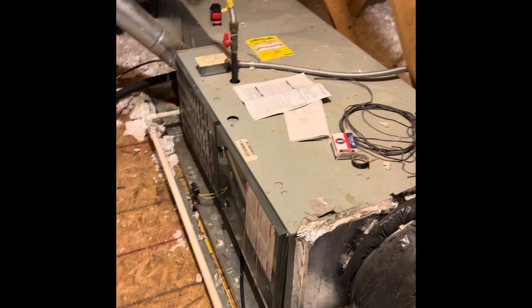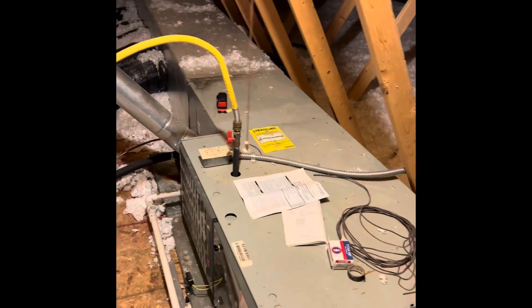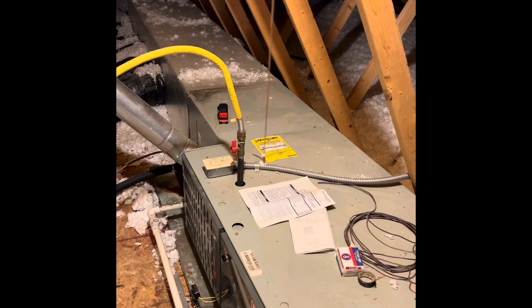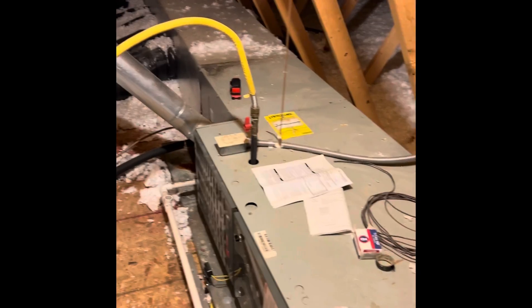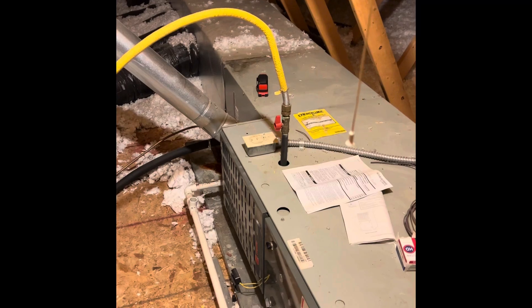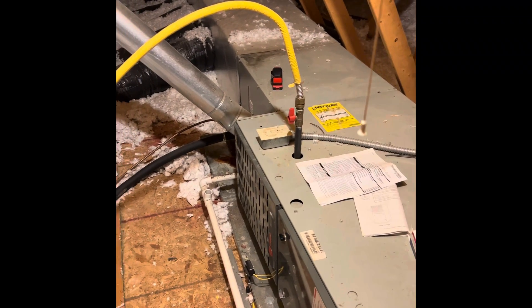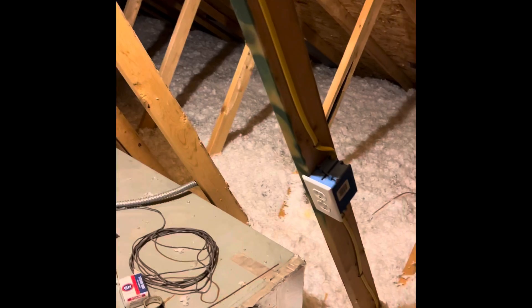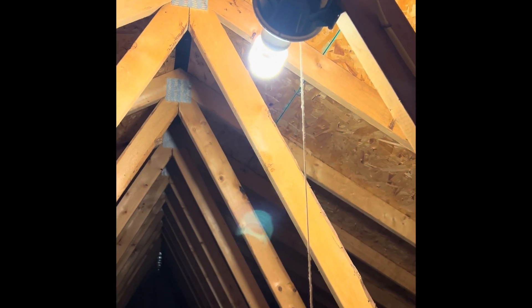The new furnace is going to lay on its side in the same location — it's a horizontal left position. Gas lines are ran and TracPipe goes into the unit. The only thing we're going to have to change is make sure there's a union outside of the unit. There's one on the TracPipe but we may need more than that. The electric switch is right there — we'll be able to reuse the existing electric switch for the air conditioner and furnace. There's an outlet up here for any type of service.